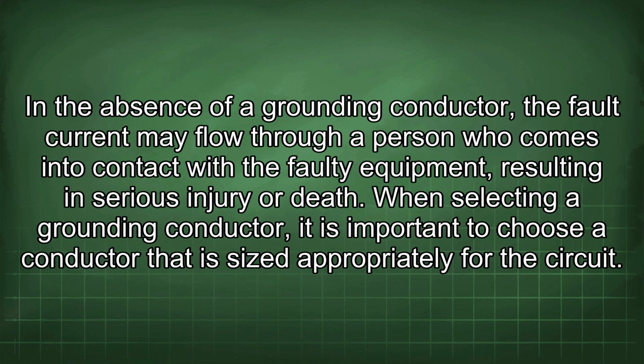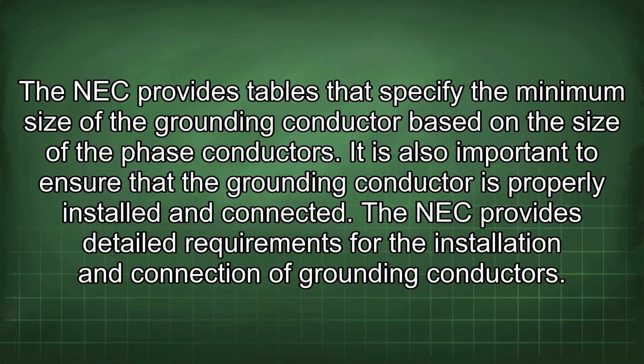In the absence of a grounding conductor, the fault current may flow through a person who comes into contact with faulty equipment, resulting in serious injury or death. When selecting a grounding conductor, it is important to choose a conductor that is sized appropriately for the circuit. The NEC provides tables that specify the minimum size of the grounding conductor based on the size of the phase conductors. It is also important to ensure that the grounding conductor is properly installed and connected. The NEC provides detailed requirements for the installation and connection of grounding conductors.